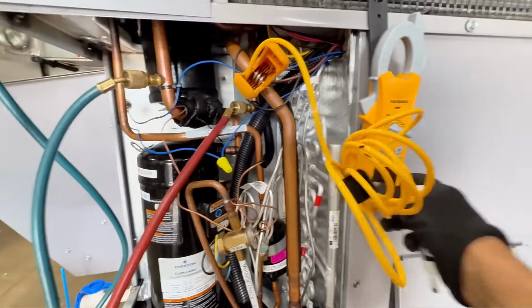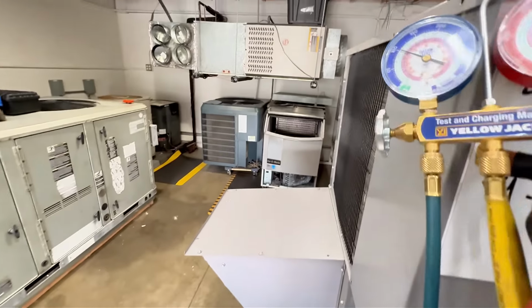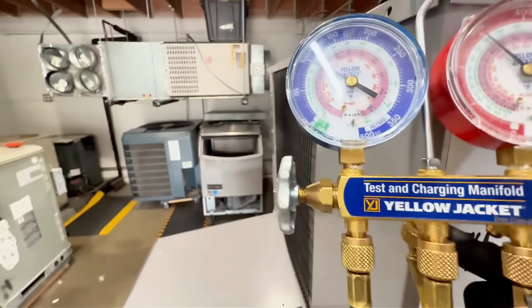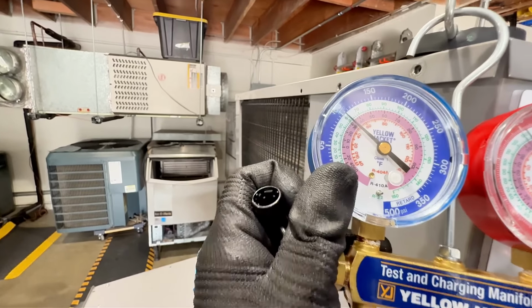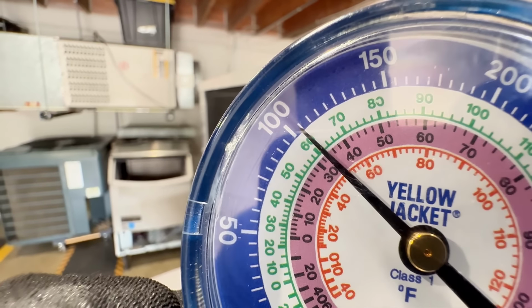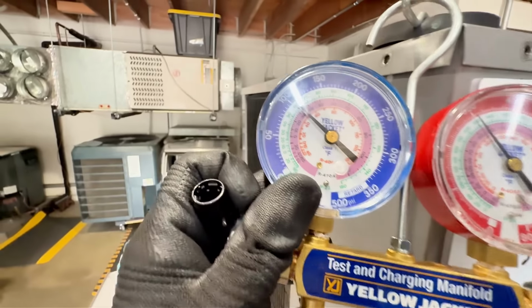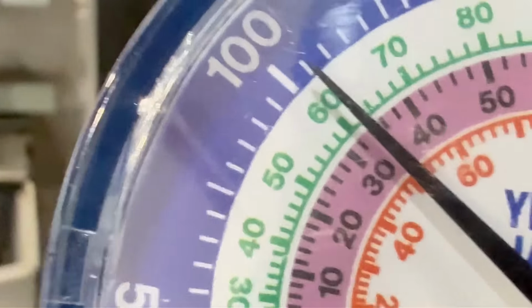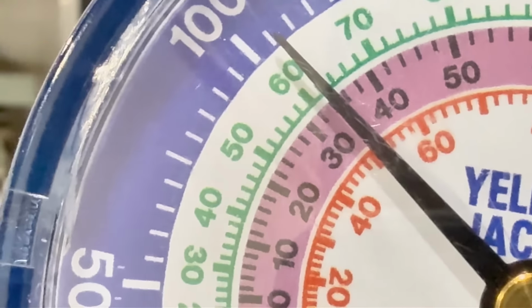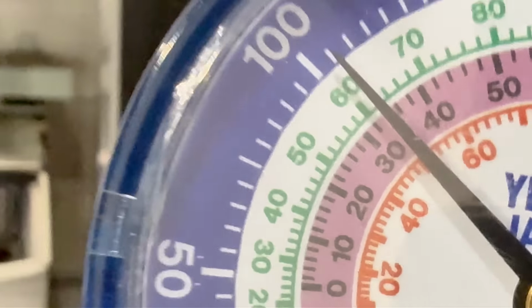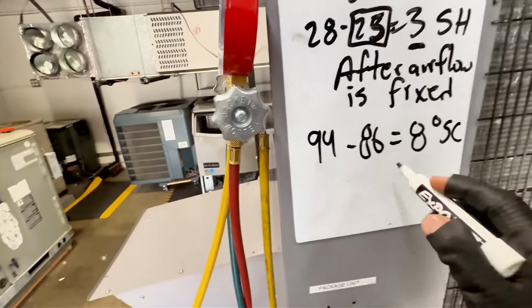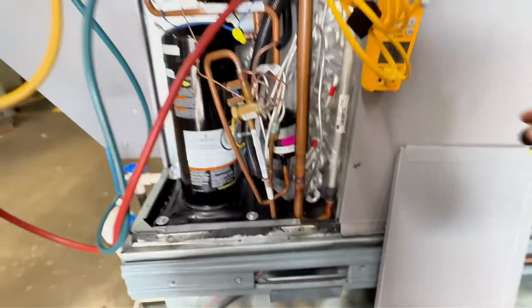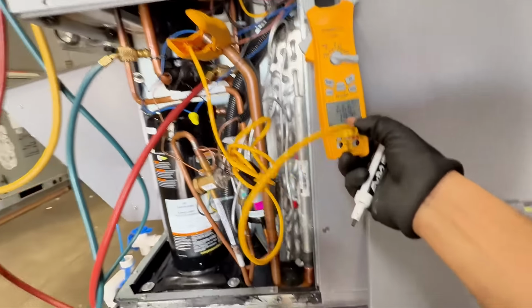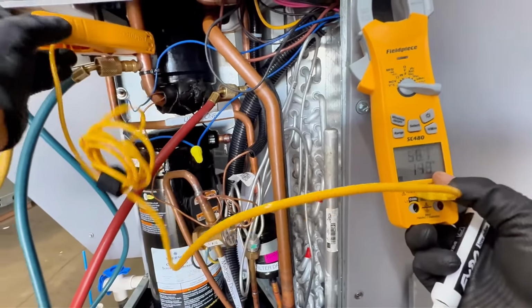Okay. Superheat is what I want you to pay attention to. We're going to let that drop right now. In the meantime, let's just give it a second. Right now, let's see if you can see, between 100 and 105 psi. And when you look at the actual evaporator temperature, let's see if I can zoom in. You see 34, maybe 35. So 34, close to 35. So a 34 degree evaporator temperature, right? Superheat is suction line minus evaporator temperature. It's still dropping a little bit. Put it right there on this one.